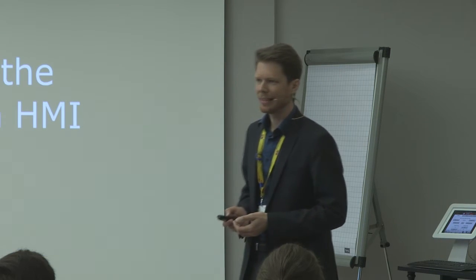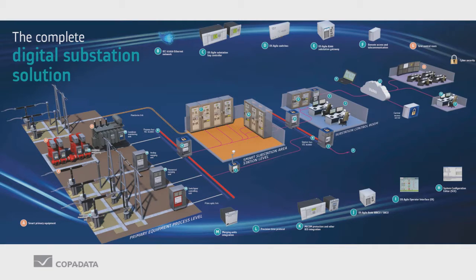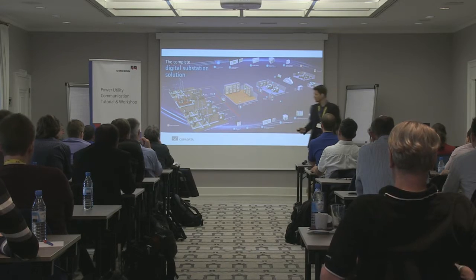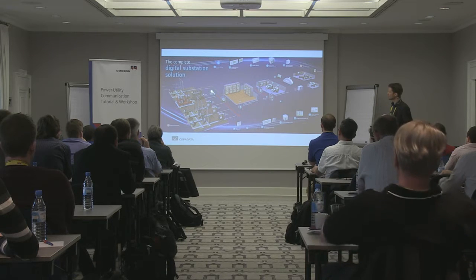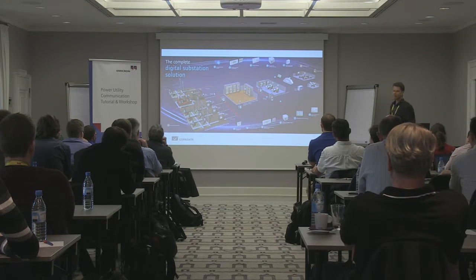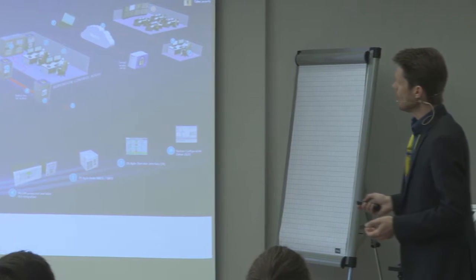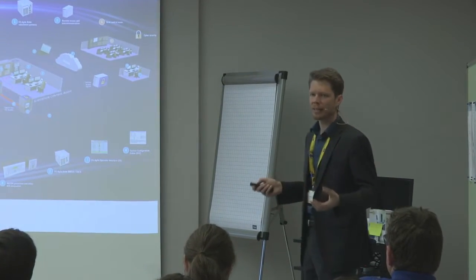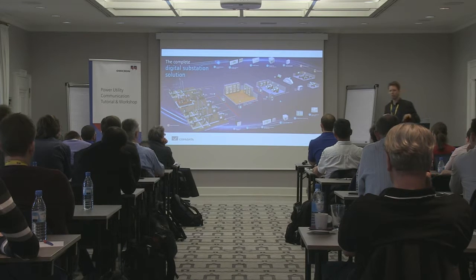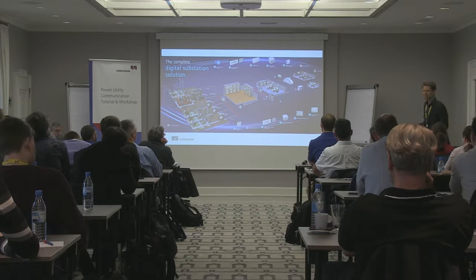Let's go into the data. I thought I should use this really beautiful drawing from a well-known company. It shows so nicely the entire world of 61850, starting with the main process on the left side, connected to the process bus, the cabinets connected to this process bus, and the hard wires if they are still available. In the cabinets we find the IEDs, protection relays and so on. And then we have the station bus — and we learned yesterday we cannot really divide the station bus and process bus; somehow they are almost the same.